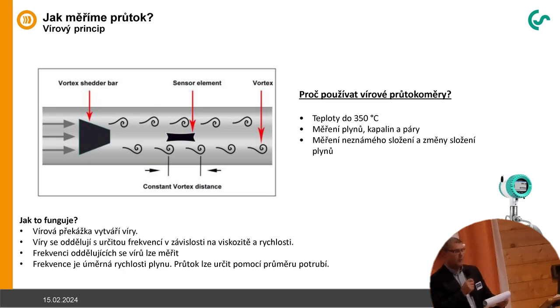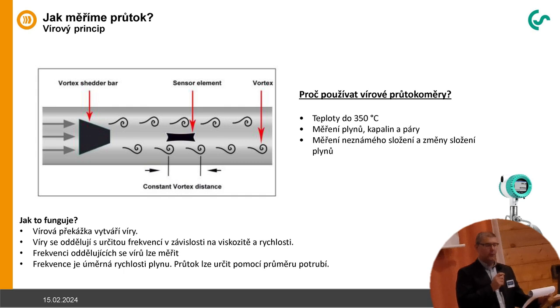The next measuring principle we offer is the vortex principle. Vortex meters are usually used up to 350 degrees, could be used in gases, liquids or steam, and they also could be used when we have to measure an unknown composition and changing gas composition. So it's a big advantage of the vortex flow meter.